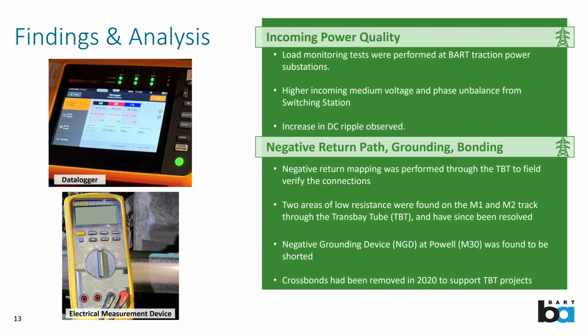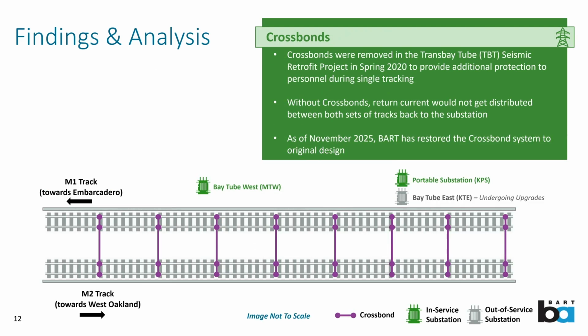I should add that because this happened in 2020 and ran in that configuration for about 4 to 5 years, this is also not considered the root cause. But taken together with the previous finding, we're looking at the cumulative impact, so this is being analyzed through load flow modeling.